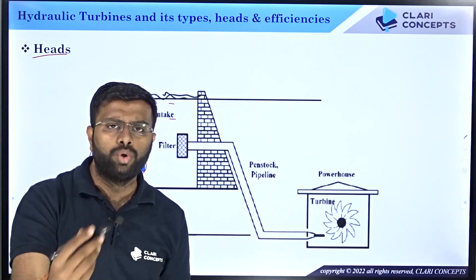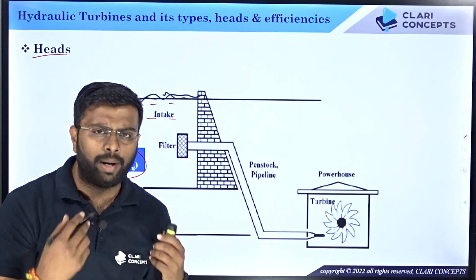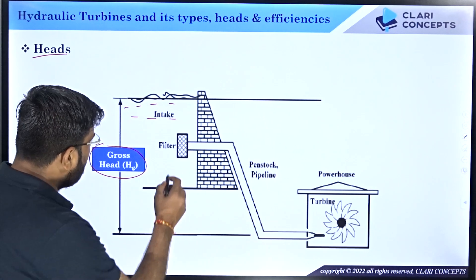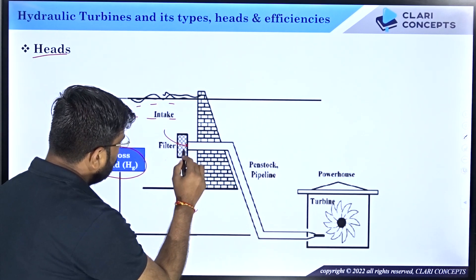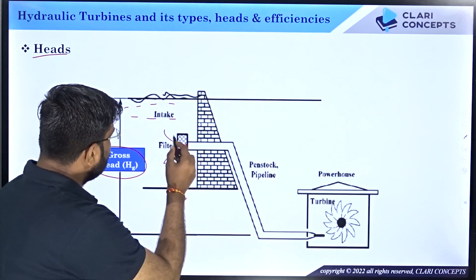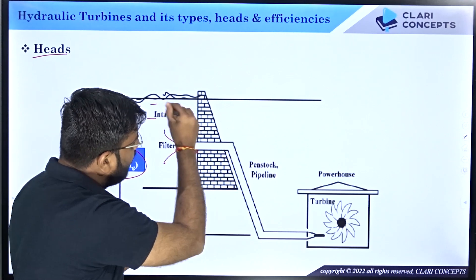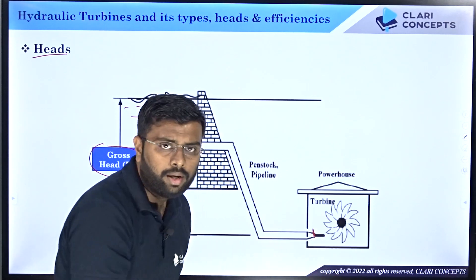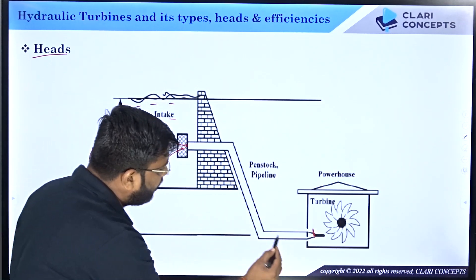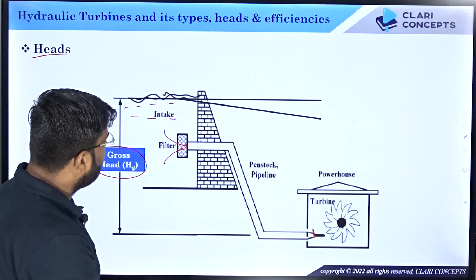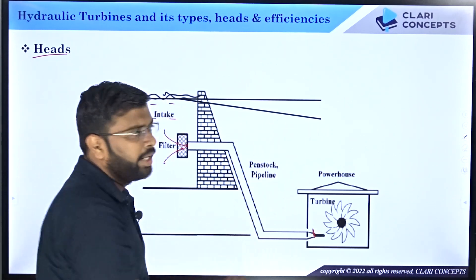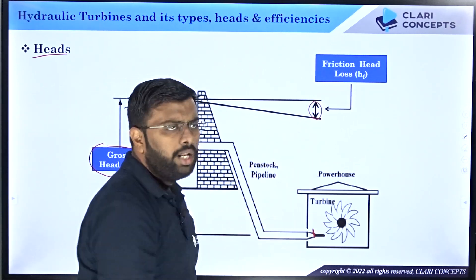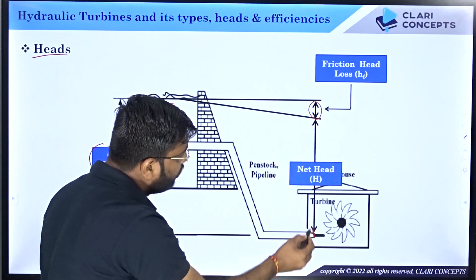As flow goes through the pipe there are many losses: entry loss, exit loss, bend loss, friction — all these losses result in an energy drop. So as water travels through the penstock to the turbine inlet, the total available head is reduced. The difference between the total available head and the head at turbine inlet we call energy loss, specifically friction head loss HF. The remaining amount we call the net head.